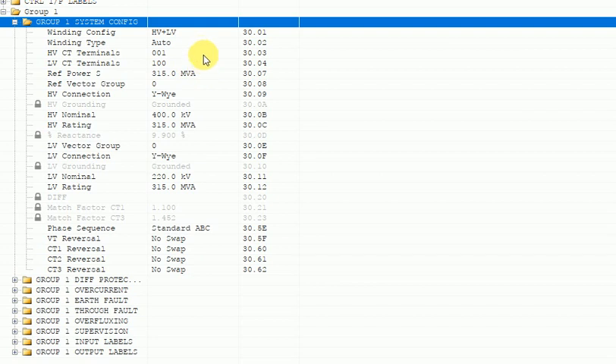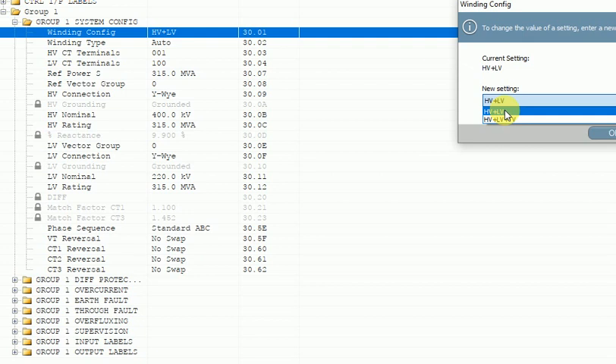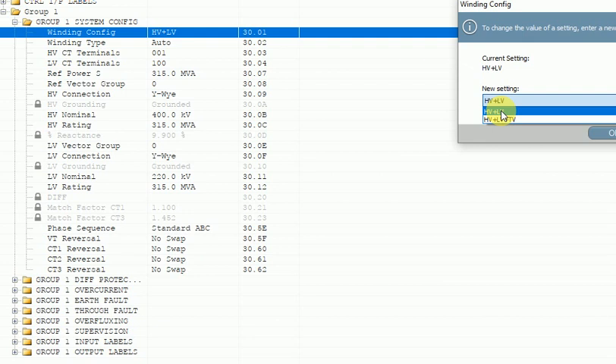In the scheme drawing there are two CTs — HV and LV. So in winding configuration we have to select HV plus LV. If you have three CTs, you can click and see multiple options. HV plus LV is for a two-winding transformer using two CTs. HV plus LV plus TV (tertiary) is for a three-winding transformer using three CTs. As per my scheme drawing, I am using two CTs, so I will select HV plus LV.